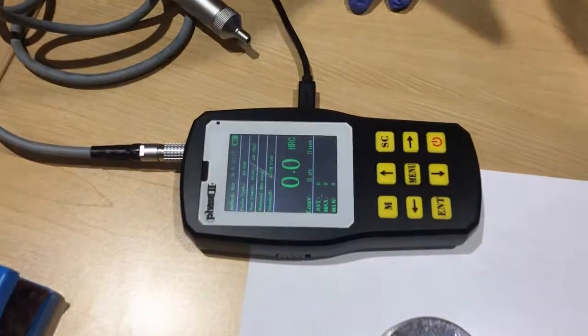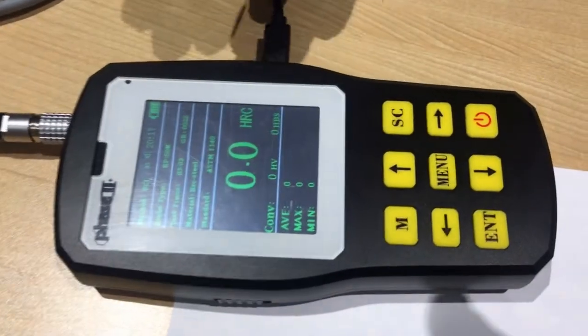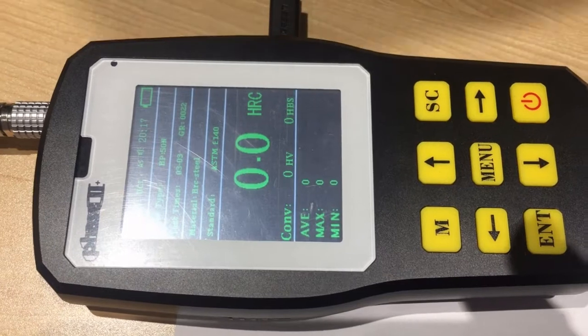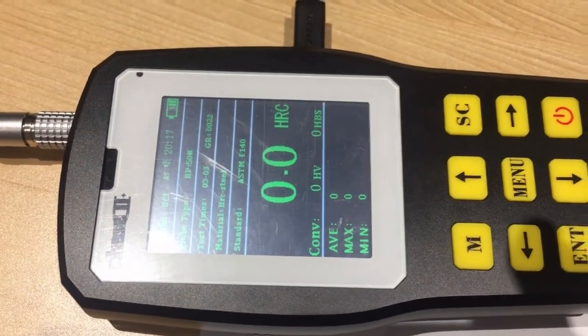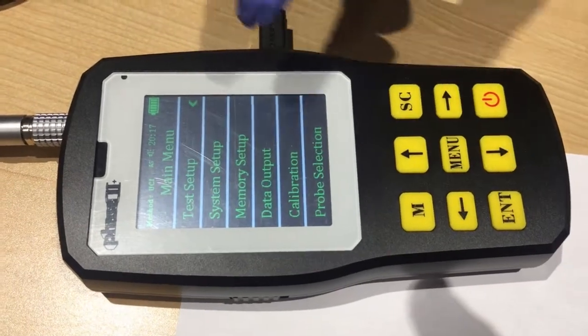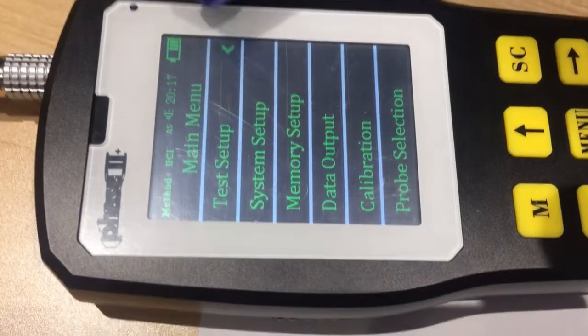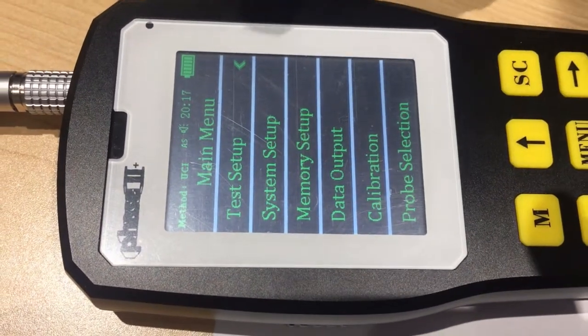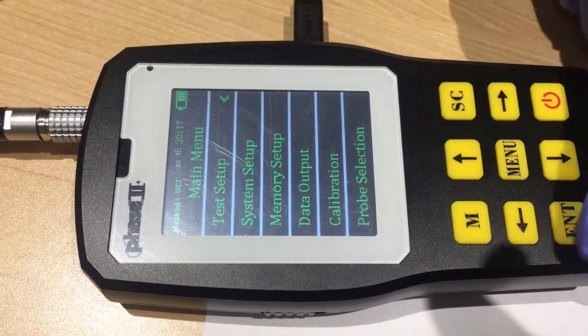Following, we are going to set up the calibration for the machine. Now we are on the main surface of this machine. Before we start, we got to set up something. So we press menu here, and we can see the following options. We choose test setup. See your cursor is on the test setup here, and press enter.